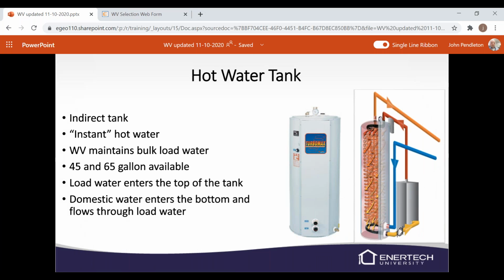The hot water tank, we kind of talked about this tank. You can't just go to your Ace Hardware and pick up a regular standard water heater and use it on the WV unit. Basically, it supplies almost instant hot water. Your load water from the unit goes into the outer jacket, the actual bulk of the tank itself. And then there's a copper pipe that's kind of coiled up inside of the tank. The domestic water from the home will enter the bottom of the tank, go through that coil that is surrounded by your 130-degree bulk water from your WV unit, pick up that heat, and then discharge out the top of the tank to the shower or the sink or wherever that hot water needs to go.